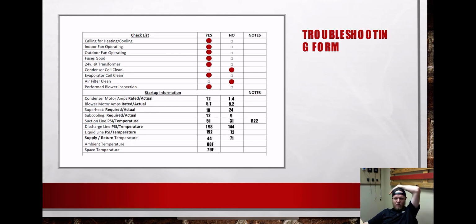Is the condenser coil clean? Is the evaporator coil clean? How do your air filters look? Performed your blower inspection, which means that you shut the unit down and you looked at your blower wheel, you looked at your belt, you looked at your pulleys, you checked the tension of your belt.